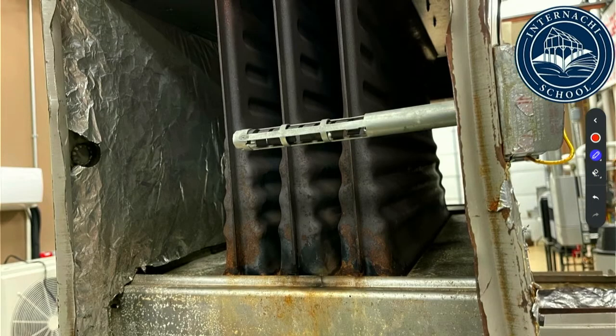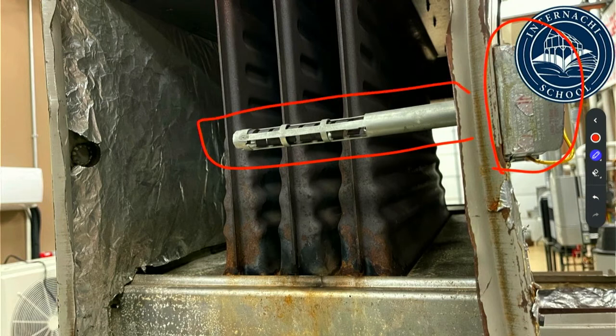This is another clamshell heat exchanger. This is our fan limit switch, also known as the high limit switch. That little disc is actually going to have this temperature probe in here. And I guess it's nice to see this, knowing that we're not measuring the air temperature inside the heat exchanger, but we're measuring the air temperature of the circulation air that's going around there. And we're going to have a data plate on this thing, and that data plate will tell you when this thing is going to go off or when it's going to trip and turn on.